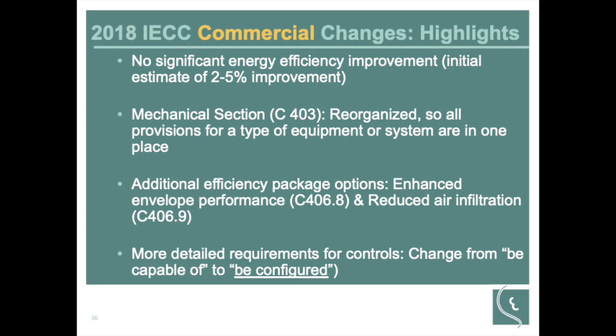The wording of that was changed from BAS systems having to be capable of doing something to them being configured to do something. What they were finding with a lot of buildings is they would be set up with a demand control ventilation system or be able to do something like that, but it wouldn't be enabled in the building, so it wouldn't actually be saving any energy. It was just capable of saving energy. So they changed the wording in the code to state that those things have to be working when they're installed.